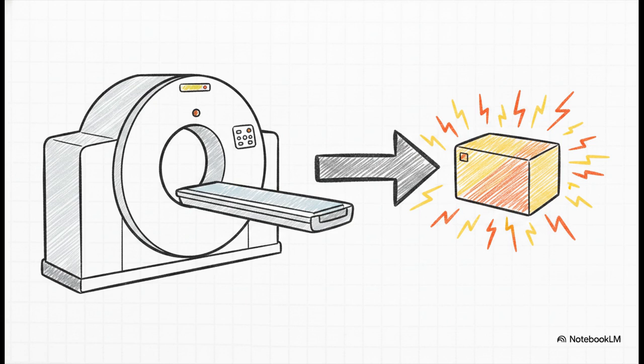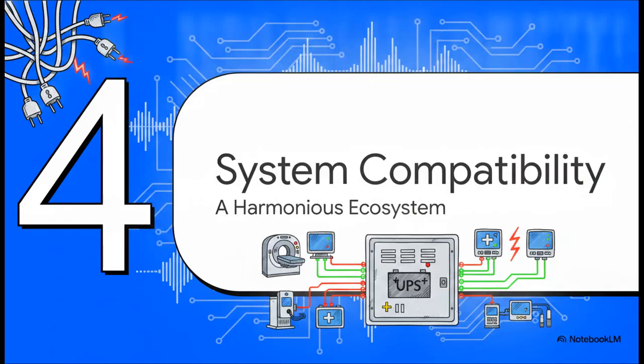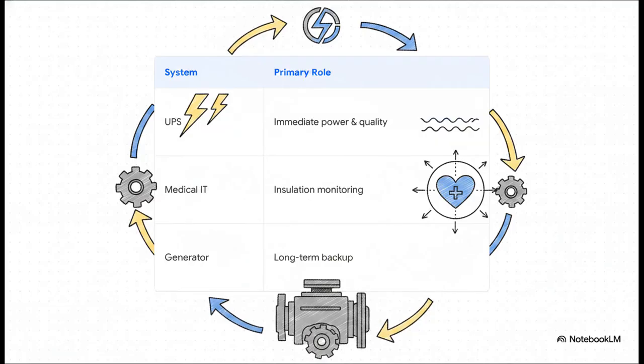This regenerative energy can easily overwhelm and trip a blindly sized UPS. If you don't use the specific manufacturer's data, your system could literally crash the moment the scanner slows down. Which leads us perfectly into Section 4, resolving system compatibility. We've got the true load figured out, but even a perfectly sized UPS is completely useless if it clashes with the rest of your electrical ecosystem.